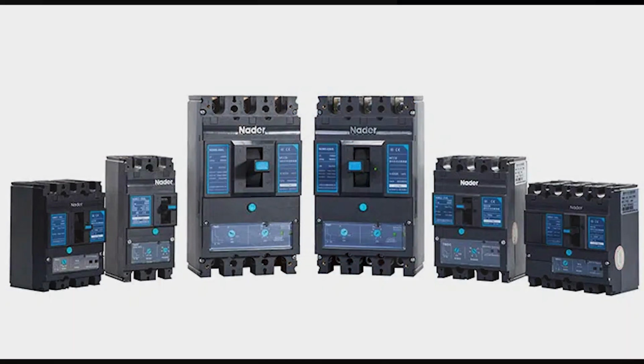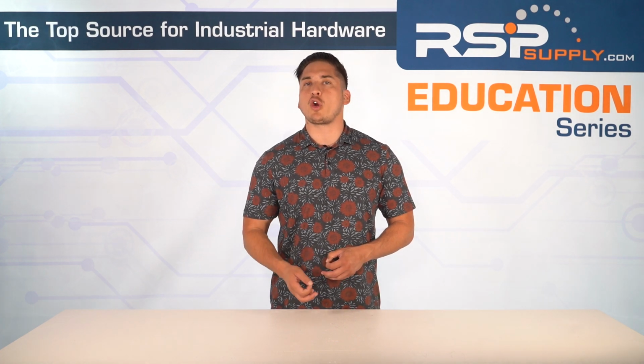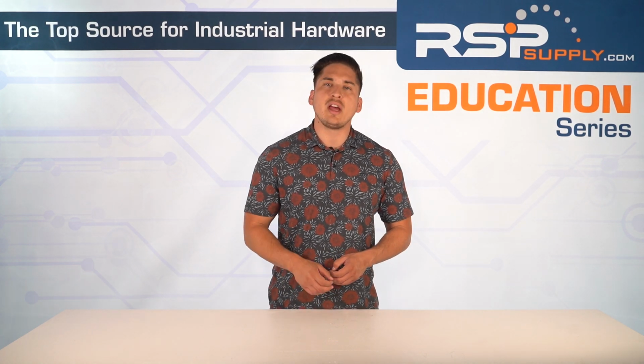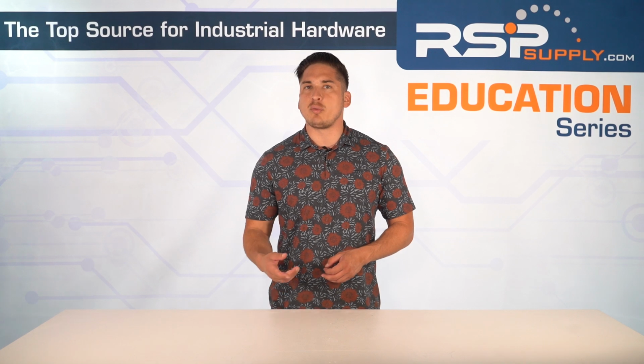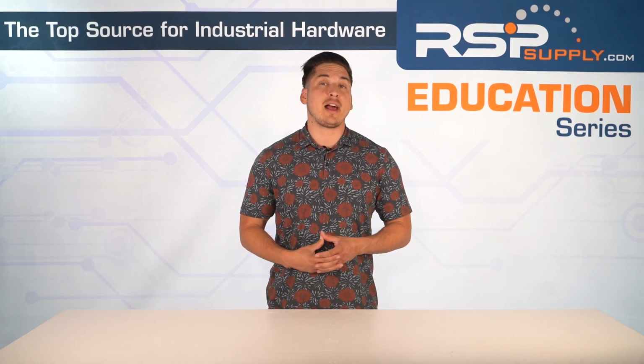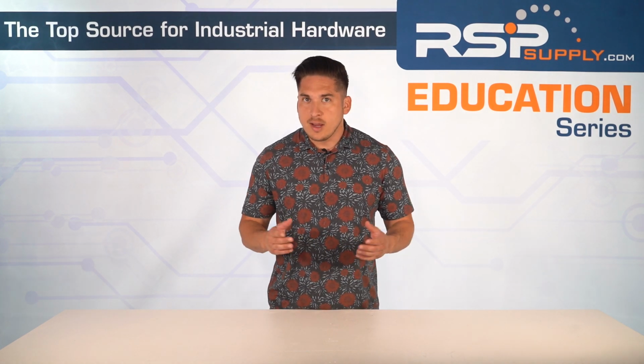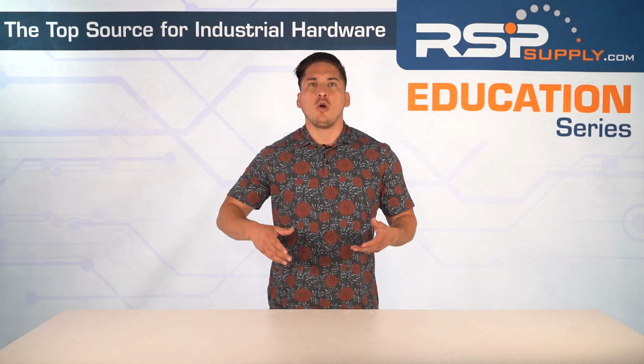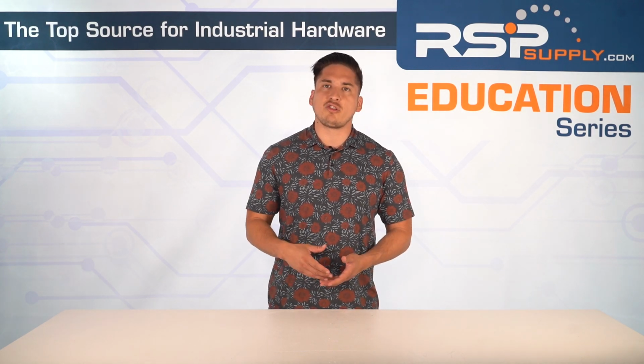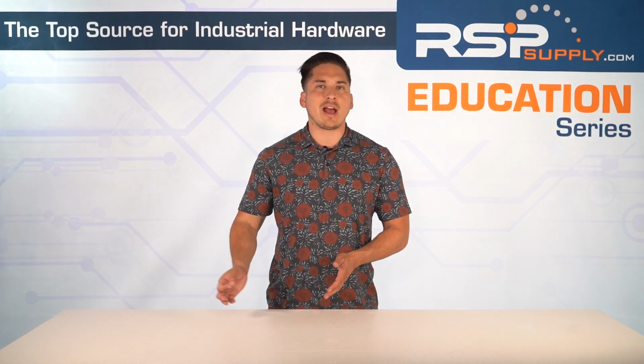Then we have molded case disconnects. It's similar to a circuit breaker but without auto tripping unless you purchase it with included optional protection. So unless you add an optional overcurrent trip unit or fuse, a molded case disconnect will not automatically shut off during an electrical fault. That's important to understand. It's meant to be manually operated, where a circuit breaker's function includes protection and switching. A molded case disconnect is primarily for switching and isolation only, no protection.